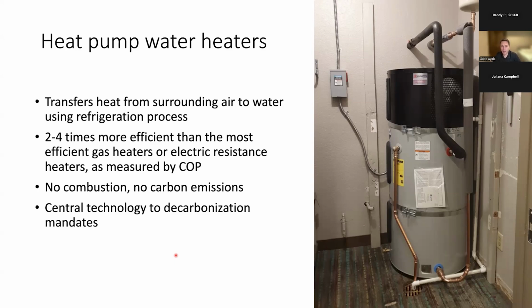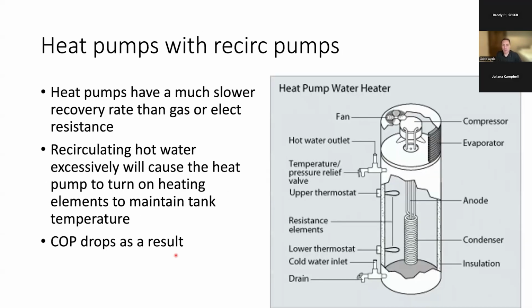And as Randy said too, the byproduct of a heat pump water heater is that it blows out cold air. It's like the reverse of a refrigerator. And in California, they're putting the heat pumps inside the garage where they have plenty of room to breathe, and your garage gets nice and air conditioned in the summertime, which people really like. However, they have a much slower recovery rate than a gas water heater. A 66 or 80 gallon heat pump water heater could take like 7 hours to get fully hot. And when you recirculate hot water through it, it diminishes or depletes the heating capacity, and then a homeowner can quickly run out of hot water.